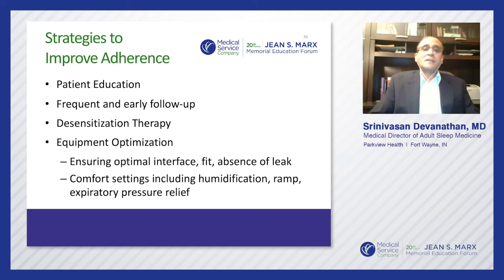Equipment optimization is another thing apart from behavioral modification, where you have to ensure the optimal interface, fit, and absence of leak. Each mask has its own leak factor too, so you've got to pay attention to that and see if there's going to be a degree of intentional leak and a degree of unintentional leak. You want to make sure that the leak doesn't exceed too much, which, as I said, consequently leads to dryness of mouth and the whole nine yards and difficulty. Comfort settings are important. Humidification, ramp, and expiratory pressure relief are very important. They call it Flex mode in some machines, EPR in some machines, but the whole concept is to provide relief in the exhalation force so that they can smoothly take their next inhaled breath.